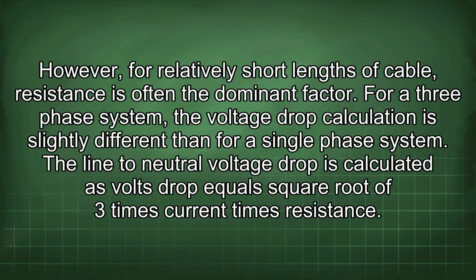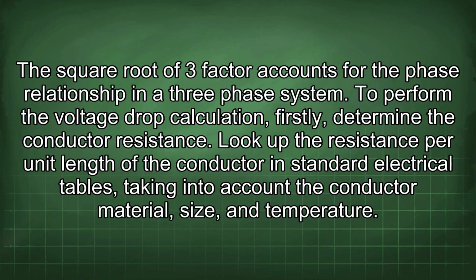However, for relatively short lengths of cable, resistance is often the dominant factor. For a three-phase system, the voltage drop calculation is slightly different than for a single-phase system. The line-to-neutral voltage drop is calculated as volts drop equals square root of 3 times current times resistance. The square root of 3 factor accounts for the phase relationship in a three-phase system.